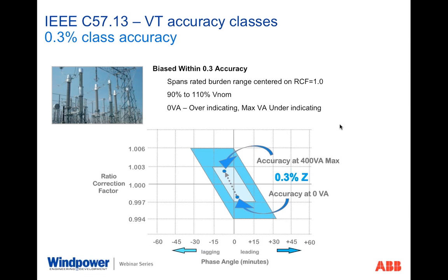And as I pass through the center region on the burden load, so for instance on Z burden, with the 400 VA burden capability, which is double Z, if I take it to Z, I'm nearly right in the center of the accuracy class. And then as I pass on up into the higher burden connections and put more burden on this device, it becomes slightly under indicating by being less than the expected 115 volts out. So accuracy is controllable in this design.